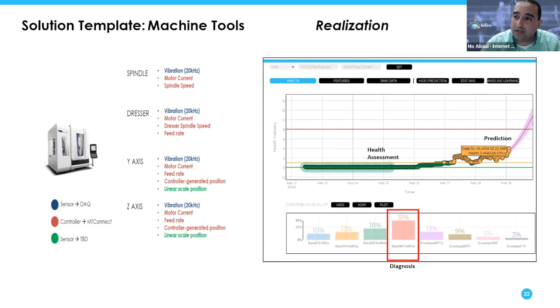There's an example of a spindle bearing prediction where the bearing was healthy. Yellow and red are automated, AI-generated thresholds. You don't need a person looking at the data; the AI has the intelligence. You don't need to invest in a certified vibration analyst unless you can afford one to look deeper into the data. Then you get a diagnostic telling you whether you're having an outer race or inner race bearing failure, and you can validate it.